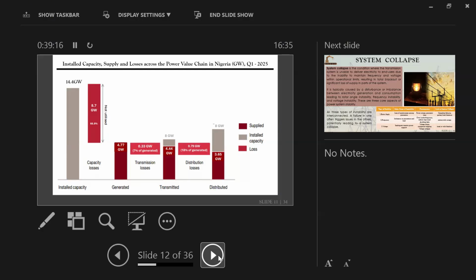Now, 7% of the generated is the transmission losses, which is about 0.33 gigawatts. 4.44 gigawatts was transmitted. About 0.79 gigawatts, 18% of generated losses, distribution losses. Then you discover that 3.65 is what got to the distributions.